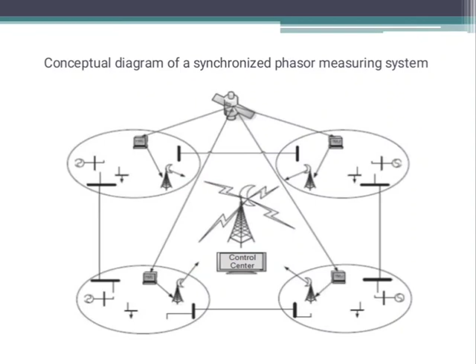That's why it is called a synchrophasor. It is also called a synchronized phasor measurement system. These PMUs are always equipped with a GPS receiver, which will synchronize the readings taken at different points. So the PMU will measure the voltage and current with high accuracy at a rate of around 2.88 kilohertz.